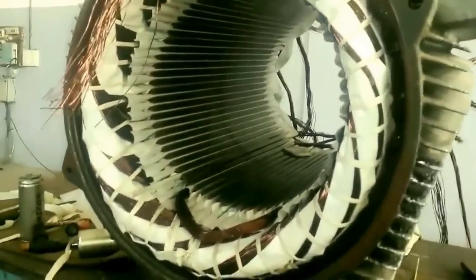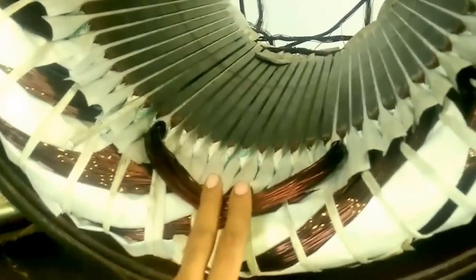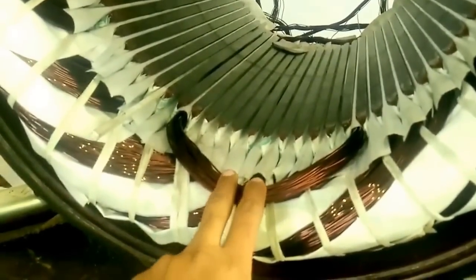You can see the lower winding here. On top of it there will be one more winding. This is supposed to be 250 kilowatt, and this is supposed to be 83 kilowatt - it's a double speed induction generator. Sorry, yeah, so the lower one is 250 kilowatt and the upper one is 100 kilowatt.